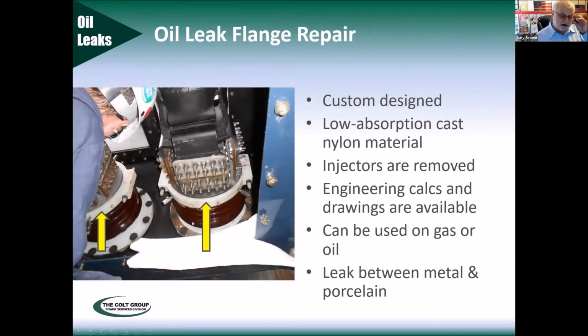So this is on a larger bushing on a generator step-up unit, where we had to close on the aluminum part of this bushing and then go over the leak and onto the porcelain. And this is how we sealed it. And again, we'd pull these and plug them when we're done. I see where a couple of them have been done.